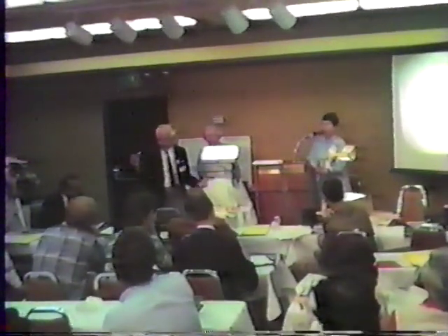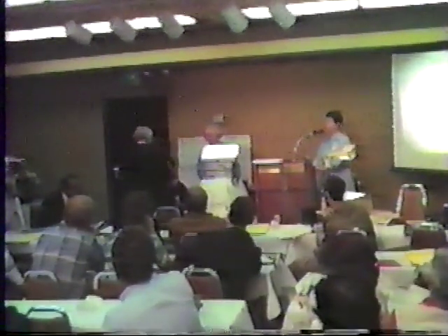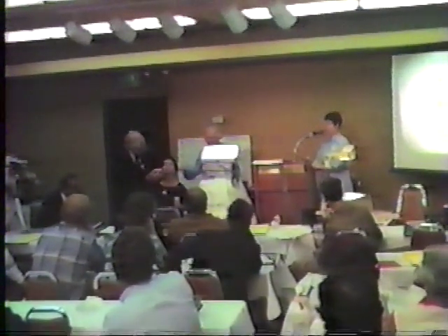When I press this knob, therapy current flows. It is the same as if I were switching the machine over to therapy, but I have a special button so I can do it directly while holding the electrode in my hand.